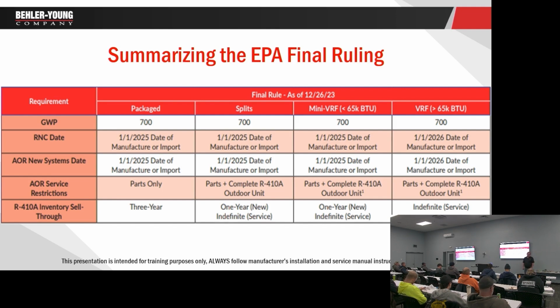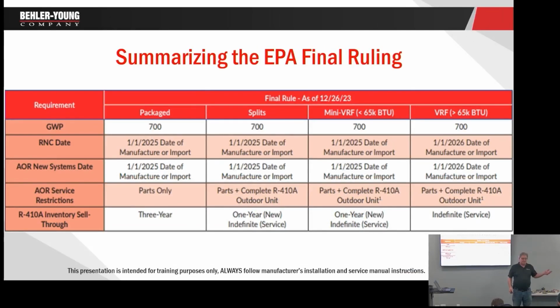As of January 1st, 2025, a month and a half ago, we can no longer produce R410A equipment for installation in package equipment, rooftop units, splits, mini splits. Okay, so package units would include geo units. It would include through the wall units. So all of that production stopped January 1st, 2025. Okay, so already we can't make it anymore. All right, so the 410 equipment is gone. All right, now we can sell through rooftop units. We have a 3-year sell through. So if they stop making it in 24, we can sell it in 25, 26, 27. Okay, but you will start seeing the new stuff phase in.